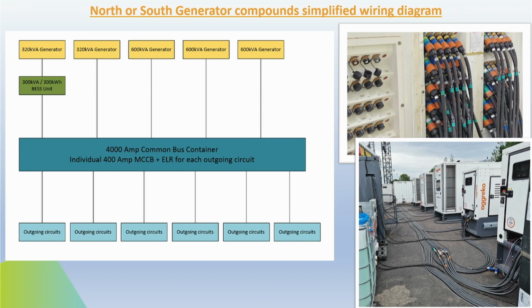But the advantage of doing this model is when it's very low load overnight and similar, the battery can power the loads, and then the other generators can be brought on stream as required as the action gets a bit busier. So we're mitigating the actual running time of the generators and the diesel burn at the same time.